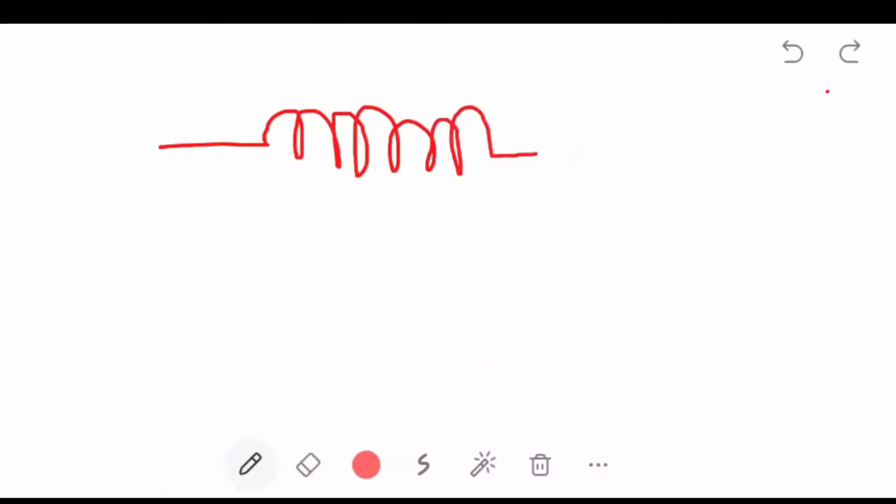That is a current differential relay. For three-phase it works the same: in the single line diagram of a single phase we use two current transformers for a single-phase transformer or single-phase generator. Generators and transformers are protected with differential relays; we have to remember that. A transformer has primary and secondary, two windings. Assume now that it is a generator.